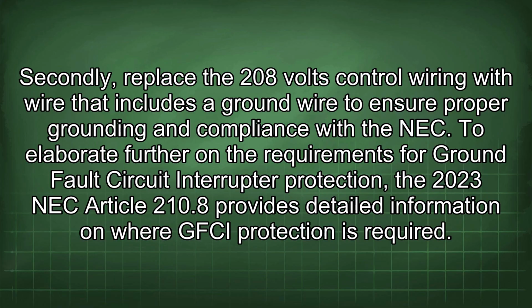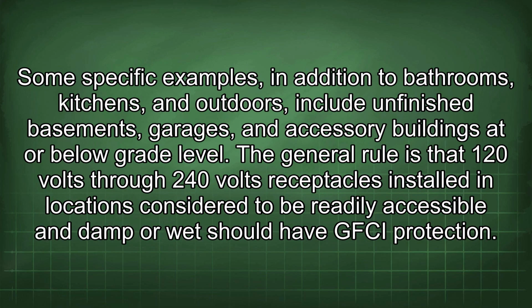with the NEC. To elaborate further on the requirements for ground fault circuit interrupter protection, the 2023 NEC Article 210.8 provides detailed information on where GFCI protection is required. Some specific examples, in addition to bathrooms, kitchens, and outdoors, include unfinished basements, garages, and accessory buildings at or below grade level. The general rule is that 120 volts through 240 volts receptacles installed in locations considered to be readily accessible in damp or wet locations should have GFCI protection.